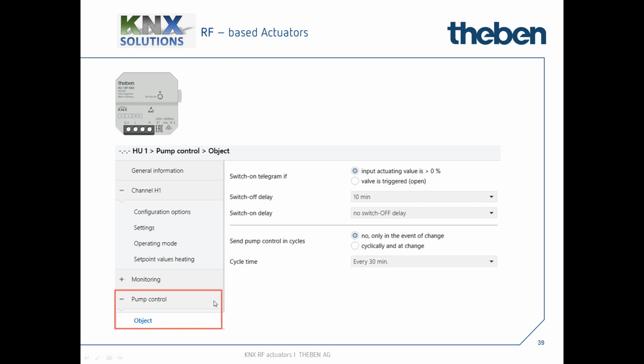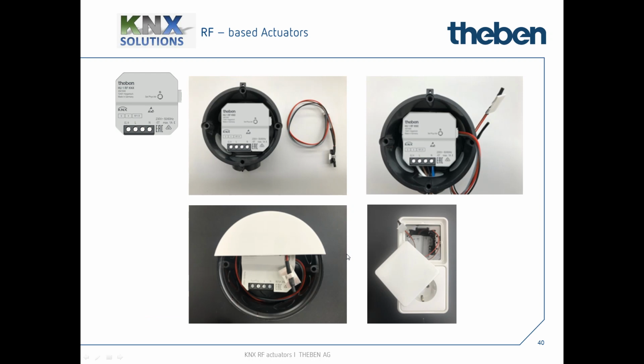Another interesting function is the support of the heating pump control. That means if the value is greater than 0, so the valve is slightly opened, you can give a bit command to an actuator, for instance, and this actuator finally drives the heating pump and brings the warm water into the heating tubes. And if the heating value is 0, the heating pump stops after, for instance, a delay of 10 minutes. So an efficient way to operate and to save energy.